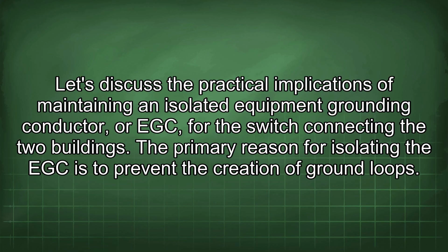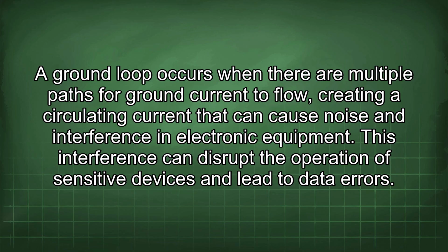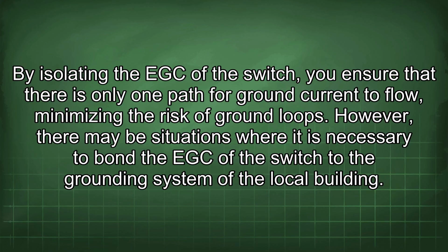The primary reason for isolating the EGC is to prevent the creation of ground loops. A ground loop occurs when there are multiple paths for ground current to flow, creating a circulating current that can cause noise and interference in electronic equipment. This interference can disrupt the operation of sensitive devices and lead to data errors. By isolating the EGC of the switch, you ensure that there is only one path for ground current to flow, minimizing the risk of ground loops.